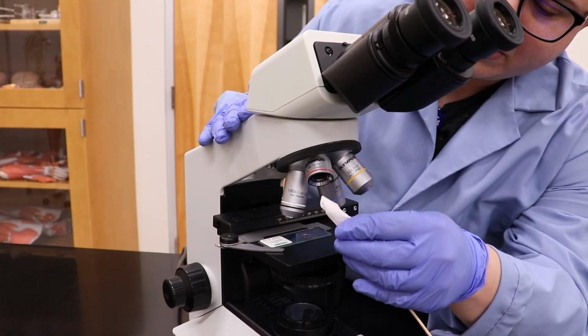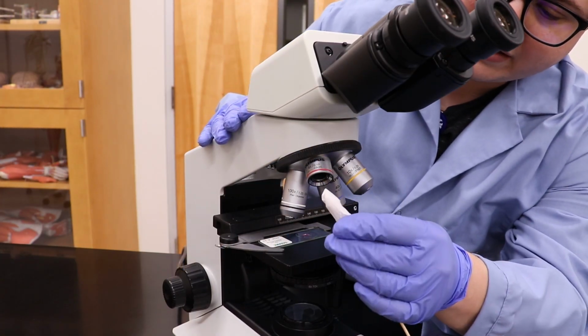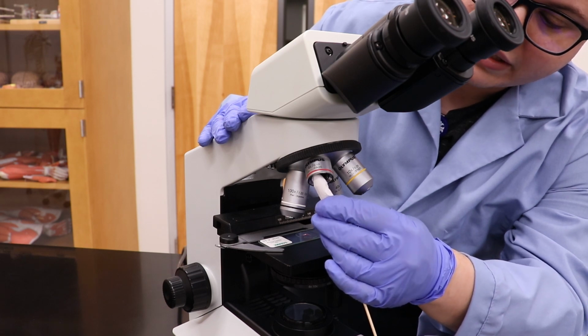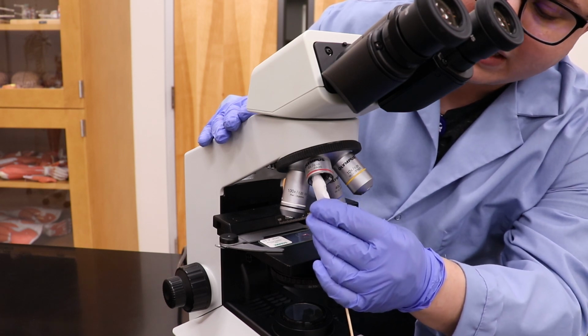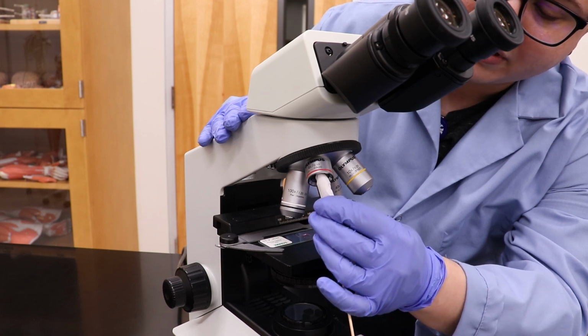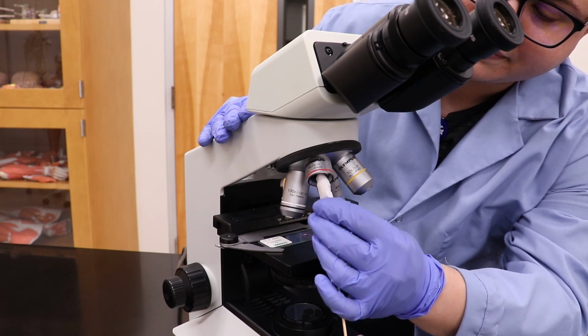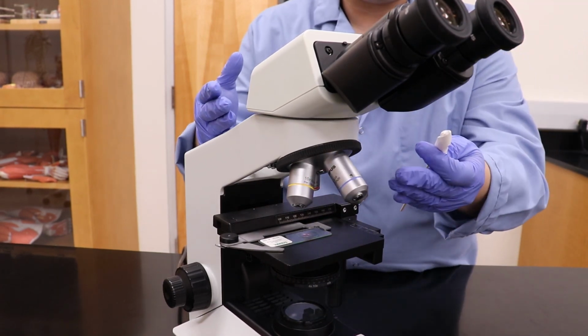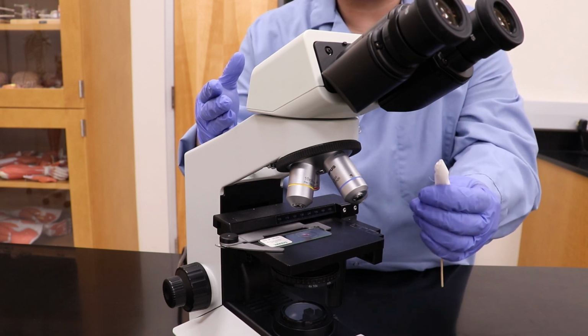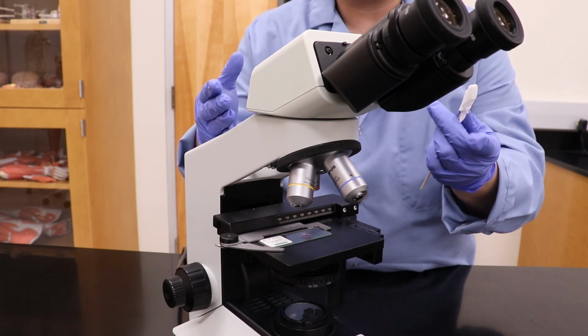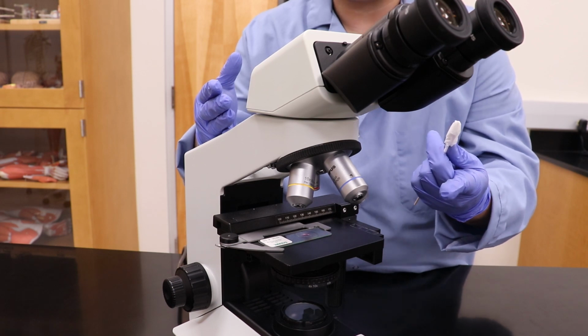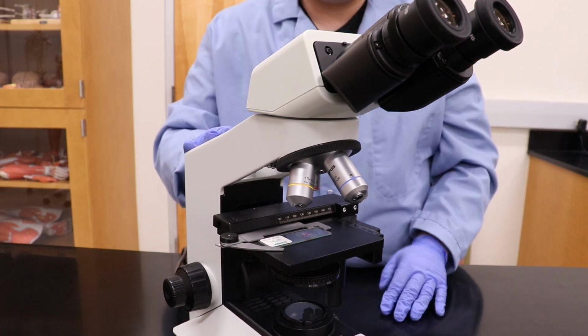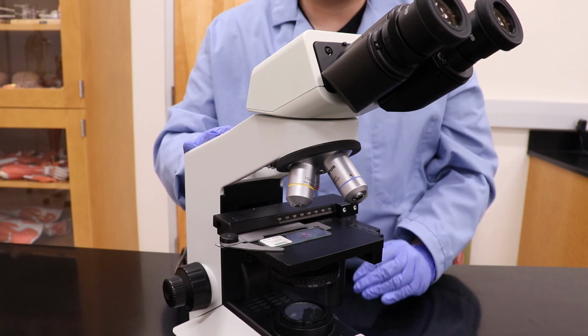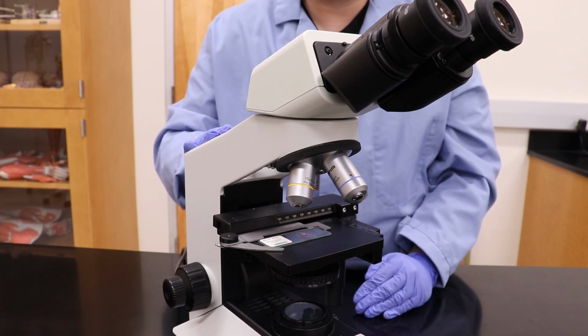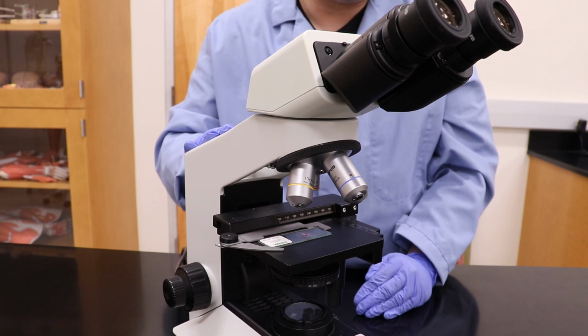So now we'll clean a lower objective. While holding the lens paper in place, you can stick the tip up inside the objective to clean the lens. You only need enough force to touch the lens paper to the lens to clean it. As we move up into higher objectives, the 40x and the 100x, you can continue to use the swab, or you can just use some lens paper wrapped on your finger like we did with the eyepieces. As we're cleaning the objectives, we want to make sure that after we clean each objective, we check for clarity to make sure that it's actually clean.